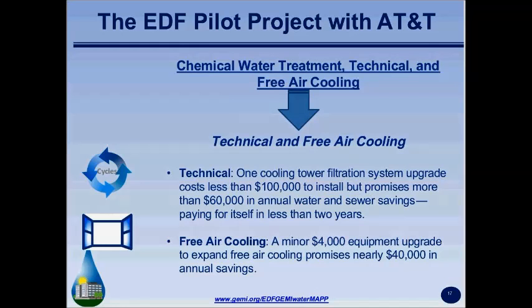For the project with AT&T, we ran a pilot phase testing three approaches. Cooling tower systems use chemicals to treat the water, because evaporation leaves behind solids that were originally in the tap water. The second approach was non-chemical treatment, like filtration systems or water softeners. The third was reducing building cooling load by taking advantage of free air cooling, or air economizers. For the pilots, we teamed up with a consultant, Bill Harfst, who had over 35 years of experience with cooling towers and water treatment programs, providing expertise and guidance throughout our work together.